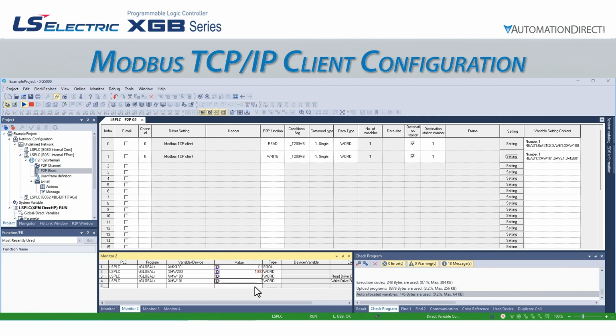If we change %MW101, which is our speed command write, to 1000, we see that the value changes in the drive and is read back to %MW100. We are now able to control our drive speed from our XGB PLC using Modbus TCP.